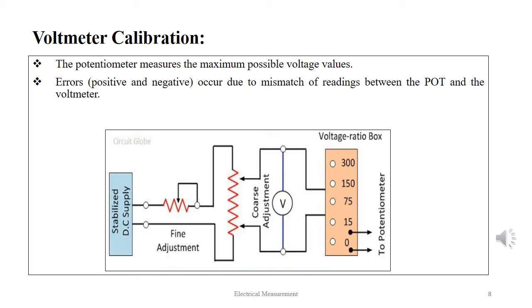As already mentioned, for voltage calibration or the calibration of a voltmeter, the setup comprises a stabilized DC supply, a potentiometer which is considered to be the standard, a voltage ratio box to step down the measuring voltage, and the voltmeter that is under calibration. In parallel with the voltmeter, we connect one coarse adjustment and one fine adjustment rheostat. The potentiometer measures the maximum possible voltage values. Errors, both positive and negative, occur due to mismatch of reading between the pot and the voltmeter.